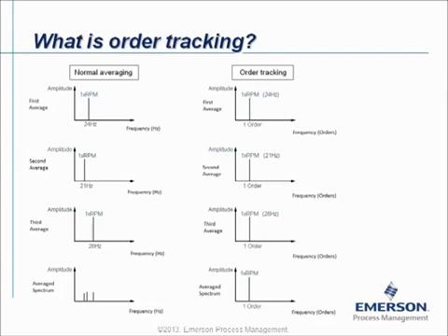Now, this methodology creates an issue when the speed is changing on the installation during data collection. Here is a good example. In the first average, the imbalance value was 24 Hz. In the second average, the speed was a little bit reduced and the imbalance value was 21 Hz. During the third average, the speed was higher again, 26 Hz. Now, if we average that, the stored spectrum will show you 3 peaks. Every peak will have 1/3 of the original amplitude, but the final stored spectrum is more or less rubbish, because the speed was changing during data collection.